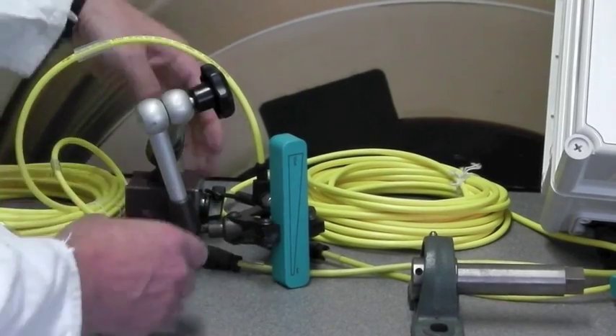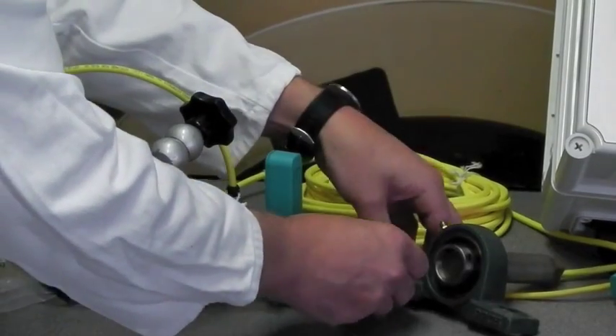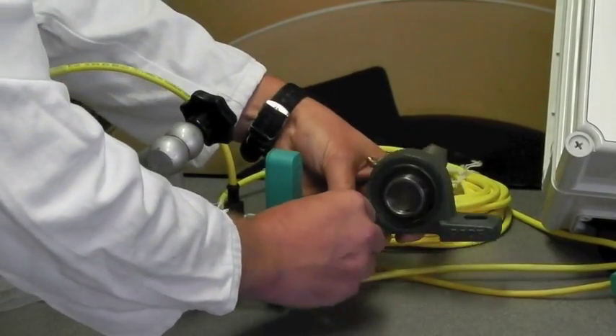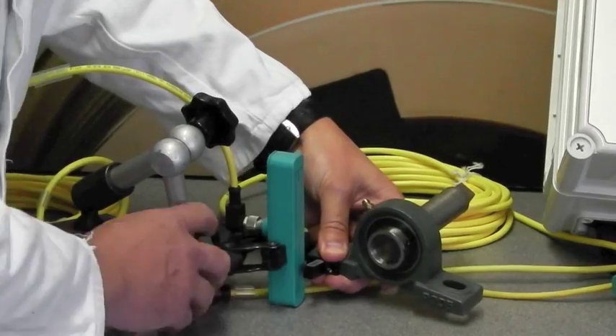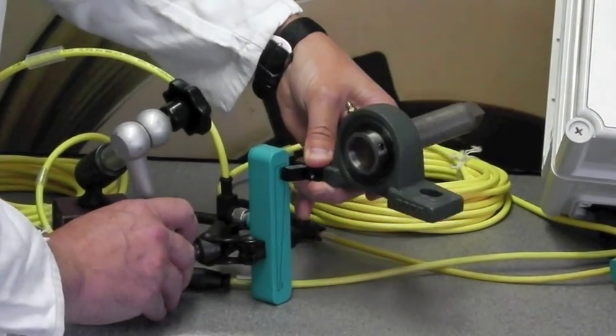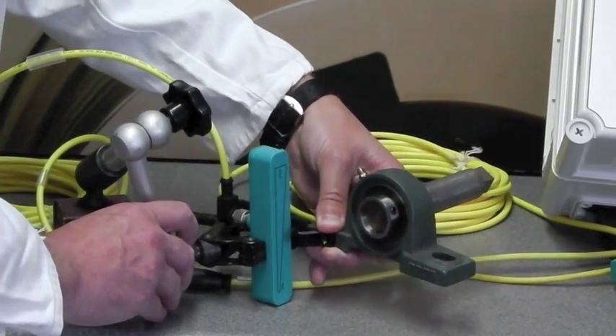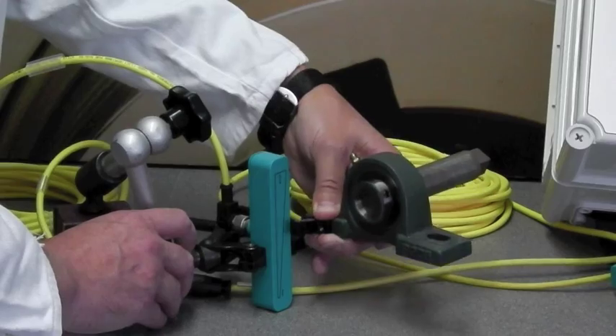So the idea is the special target will be mounted directly from the bearing, and as the target moves up and down the sensor like this, we'll get a reading as to the true position of where the bearing is.